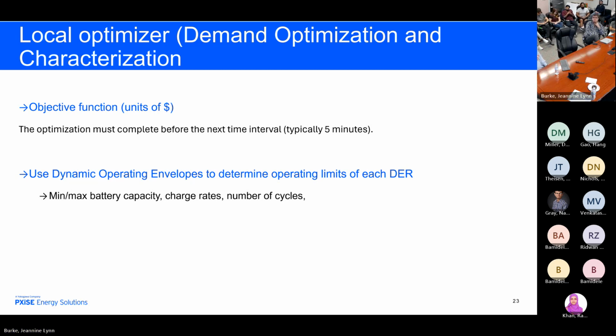Now, there's one other thing I want to mention: the term dynamic operating envelope. This is mandatory in Australia. It's never been heard of in America. Dynamic operating envelopes, I think, are very important. What they do is they allow an individual microgrid to do its own estimation of what its operating envelope can be over the next 24 hours without violating any of its constraints. Now, that operating envelope can be given to its parent, saying, here's my operating envelope. Please give me some operating instructions over the next 24 hours that are within this operating envelope.